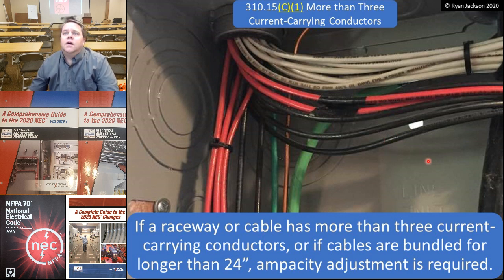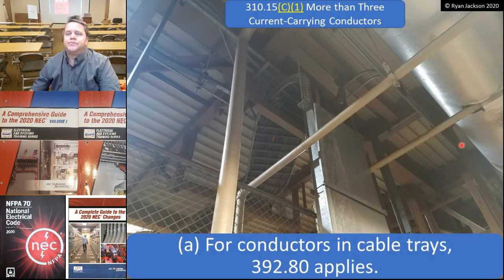So looking at this photograph, we've got quite a number of conductors in it. We've got at least 9 or so ungrounded conductors, and it looks like a similar number of neutral conductors. And what we're going to be focusing on is which of those conductors I have to count when it comes to current carrying conductors.